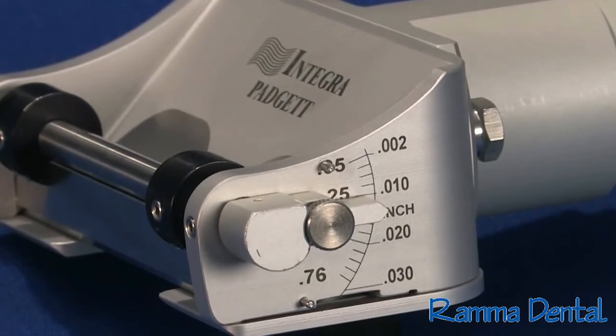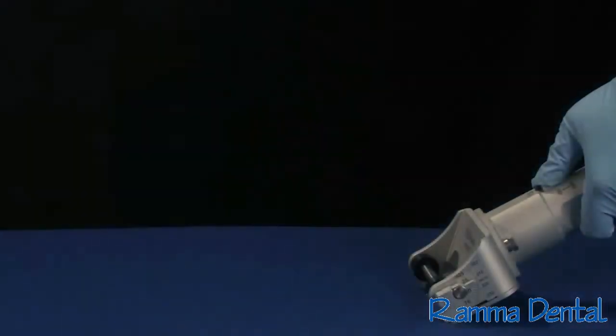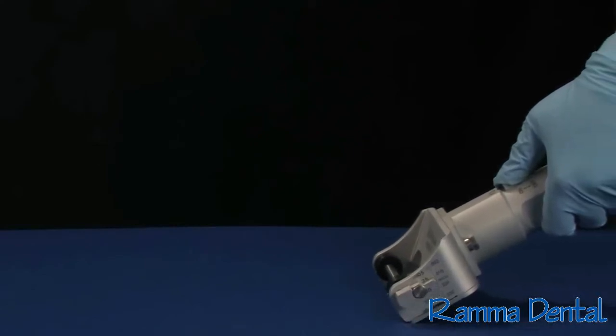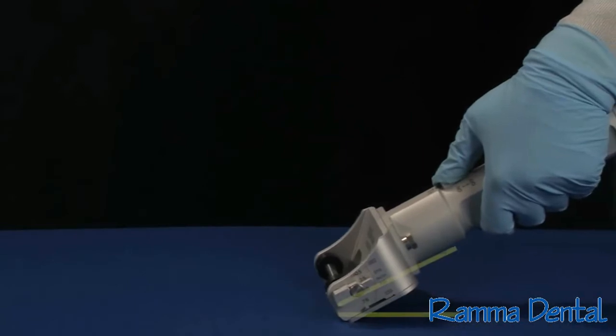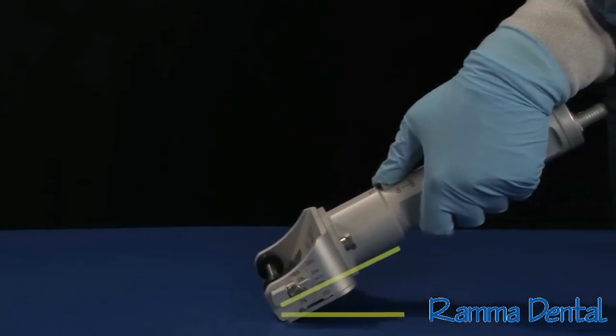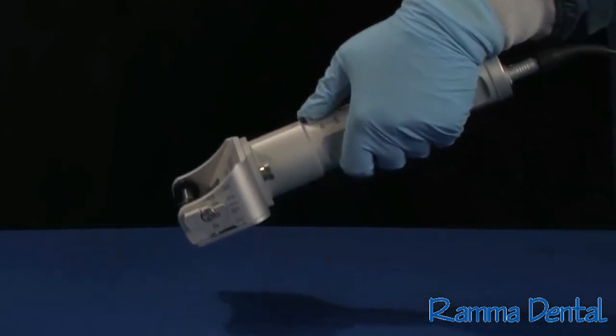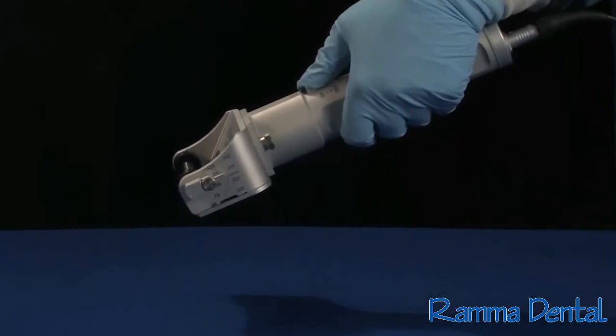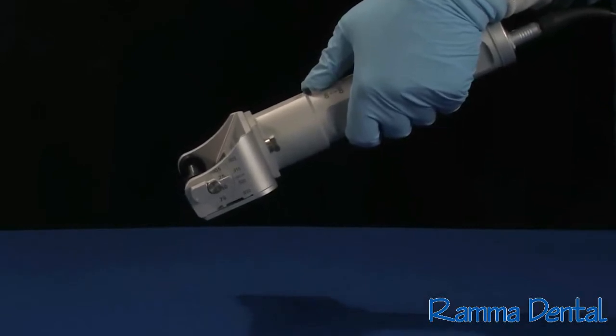Note that the actual thickness of the graft taken is largely dependent upon surgical technique and may vary from user to user. Much of the weight of the motor should be carried by the hand that holds the dermatome, so as to maintain a reasonably light pressure between the cutting edge and the body of the patient. The instrument should be held at a 25 to 45 degree angle. To sever the graft, lift the dermatome up and away from the donor site.